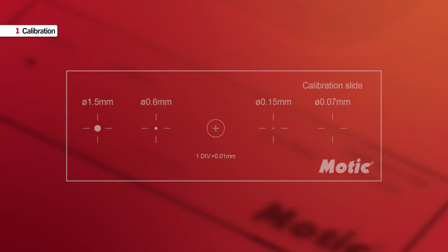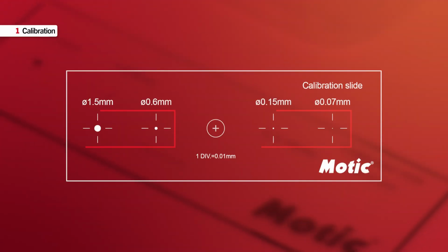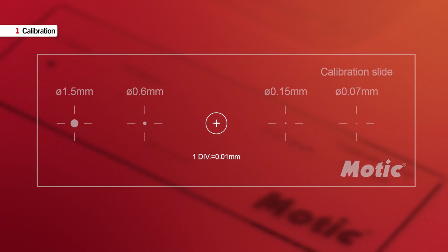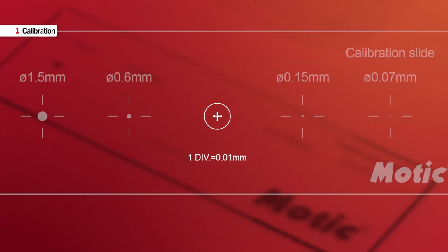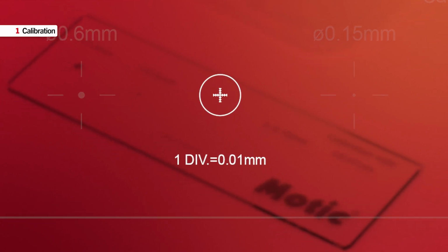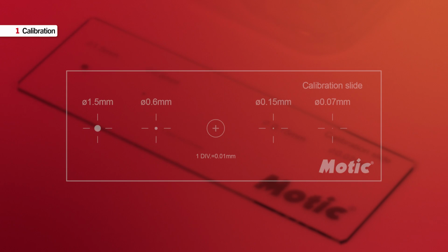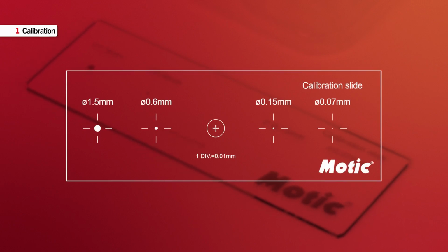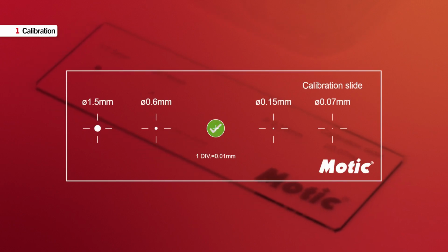On the calibration slide that comes with the camera, we can see 4 dots with different diameters and, at the center, a micrometer cross consisting of 1 millimeter divided into 100 sections. So each division equals 0.01 millimeters, or in other words, 10 microns. For this calibration process, we'll be using the micrometer cross. Let's go through the steps.